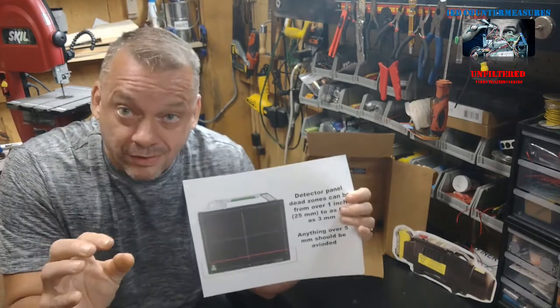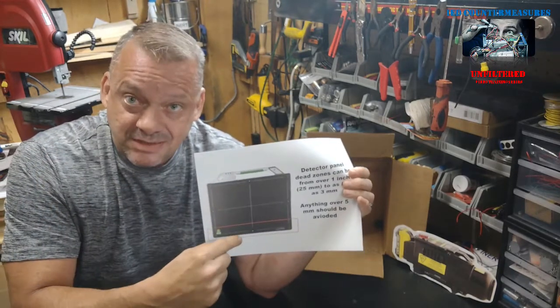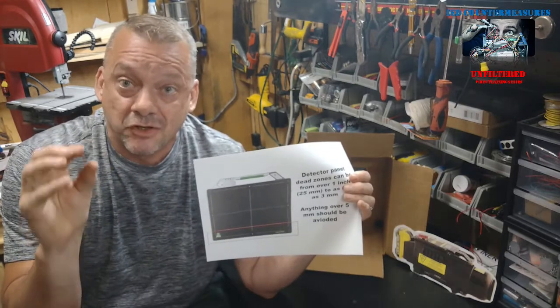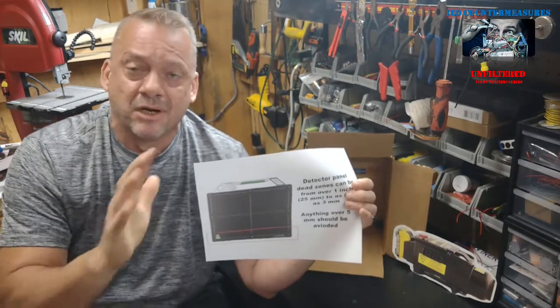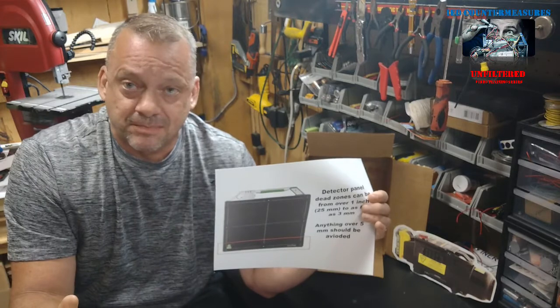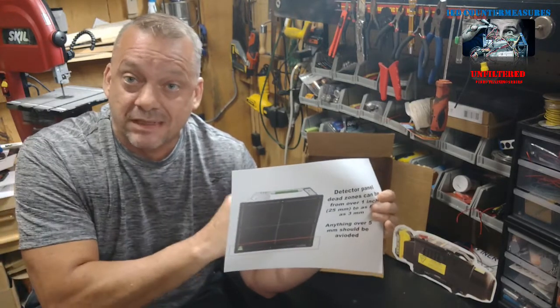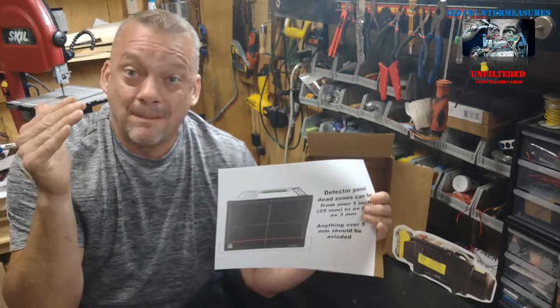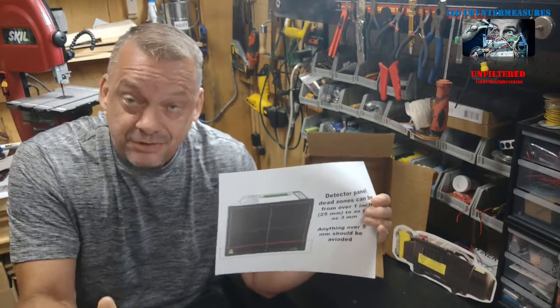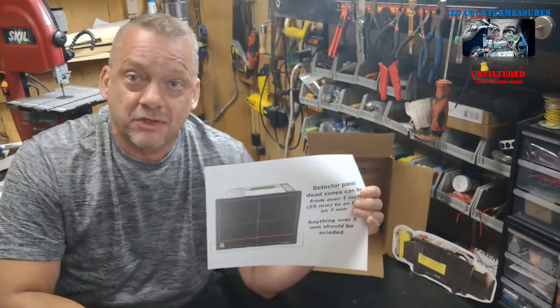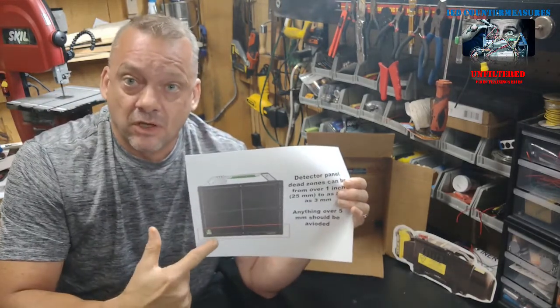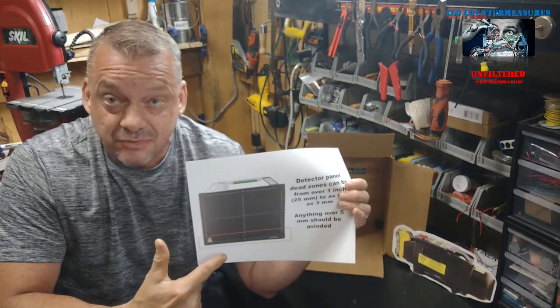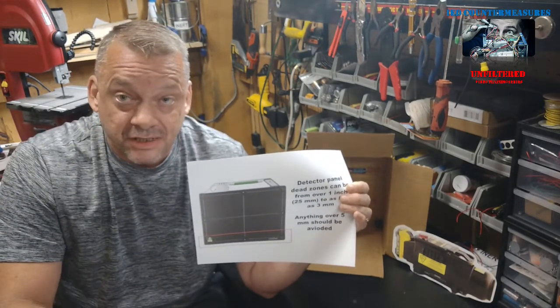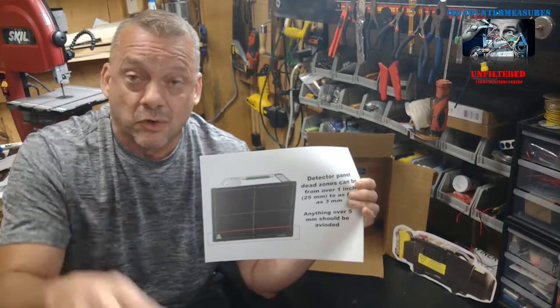So what's important is not the panel's dead zone, it's what you get in your x-ray image. Remember, I don't care what the technical specification is on a piece of equipment that's part of your x-ray system. What matters is how it correlates to your actual x-ray image. So with lower edge dead zone, just because it says it's 3 millimeter, does not mean you're going to get 3 or 5 millimeter in your image.